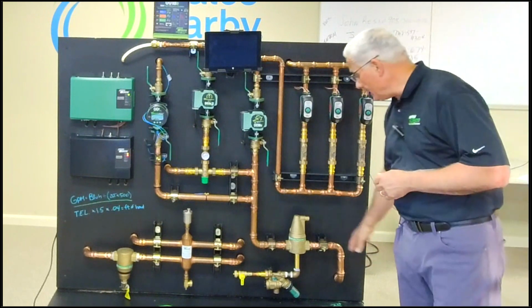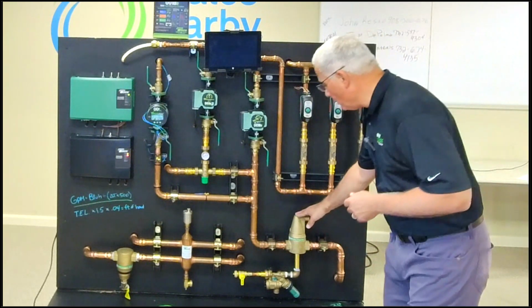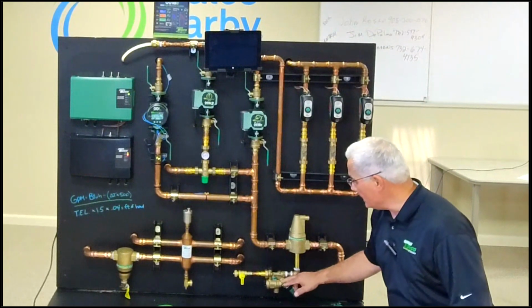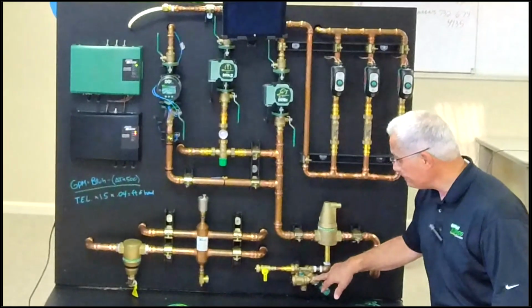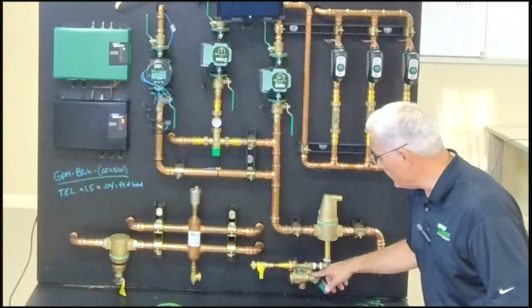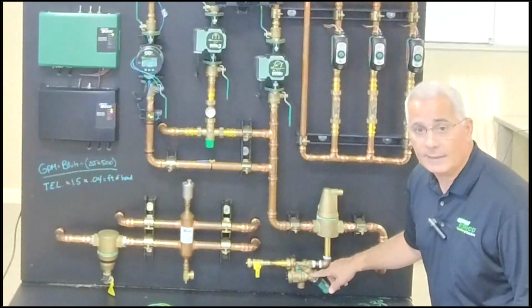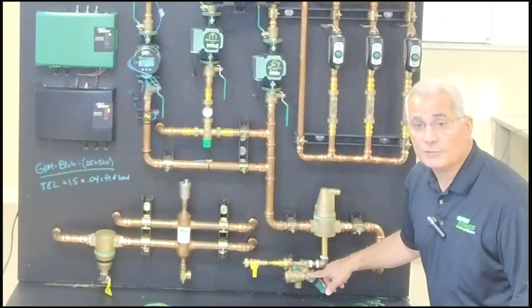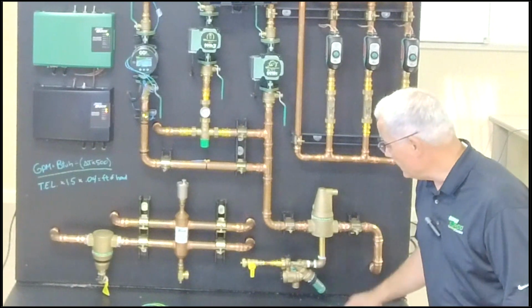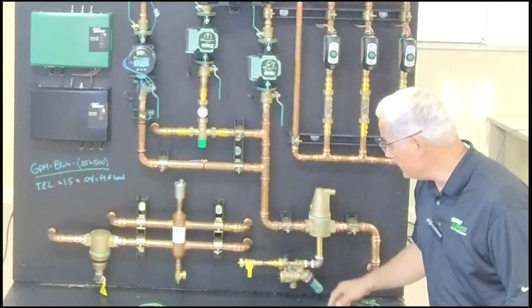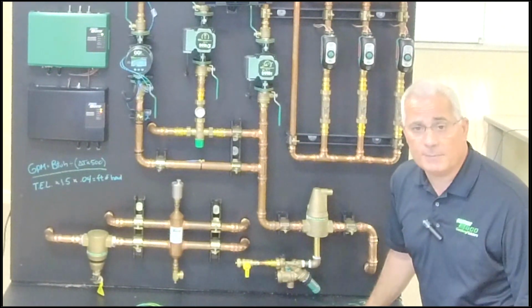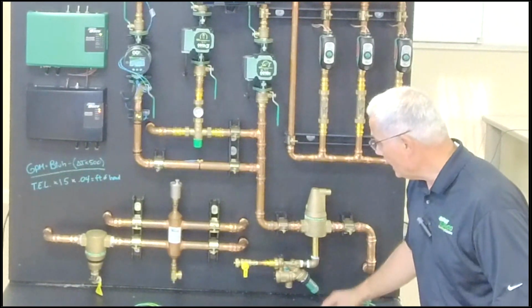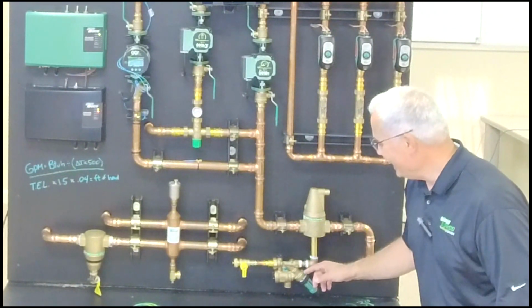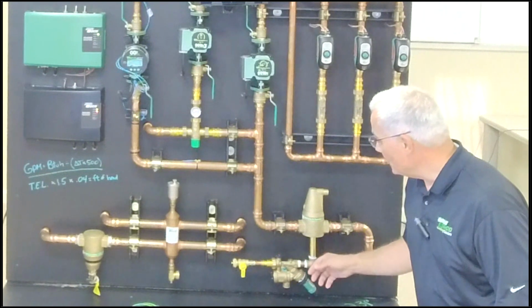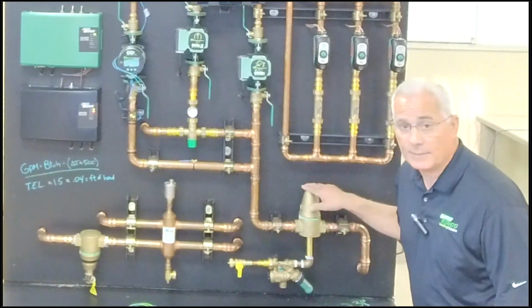So my incoming water is coming in through here. This is where I'm going to set my system pressure. This is the Taco 3450, which has the combination backflow and pressure reducing valve in here. The fast fill feature is built into this. We can take this from 5 PSI to 50 PSI. And we're also connected to our air separator.